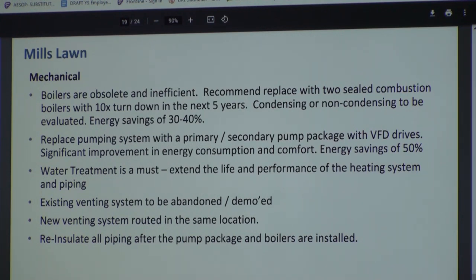I think you're doing it. On the existing venting, if you go back with an 80% efficient boiler, I would probably vent it the same way it's vented now. If you go with a 90% efficient boiler, I would vent it differently. Again, the pipe needs to be insulated, that's not insulated, and I would do that after you replace the pump package or the pump system.